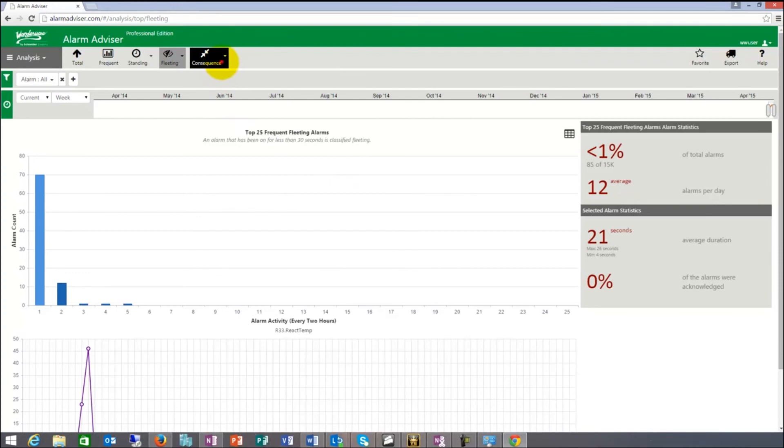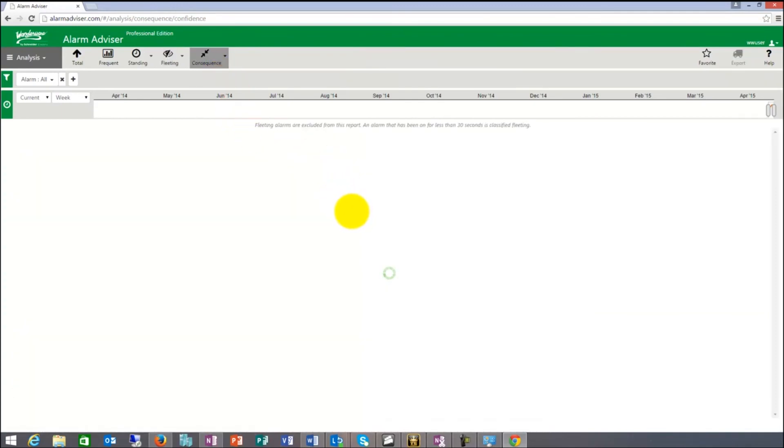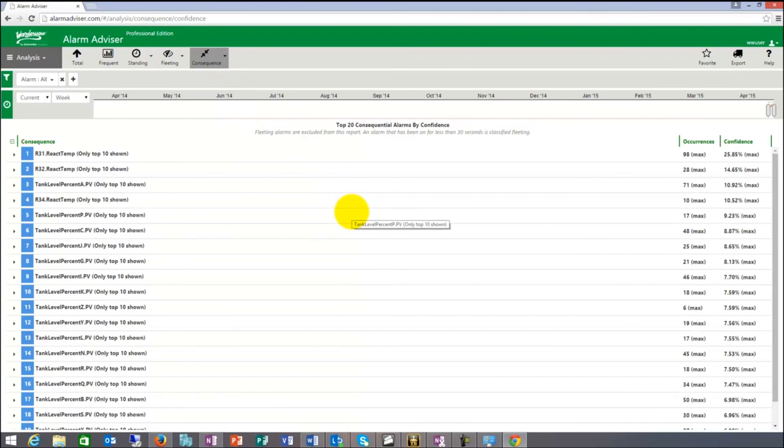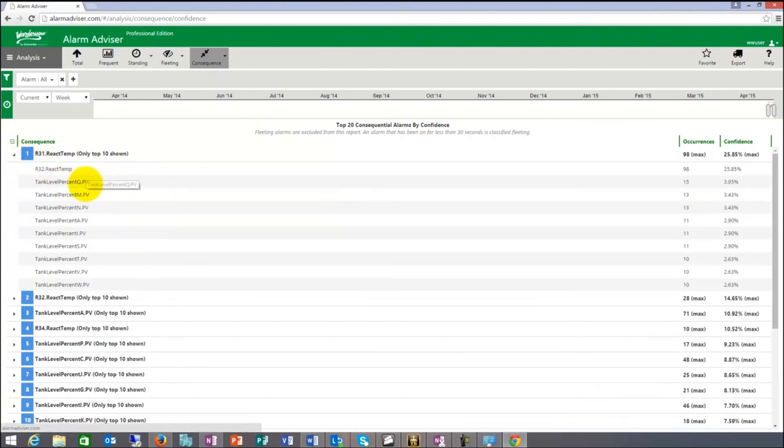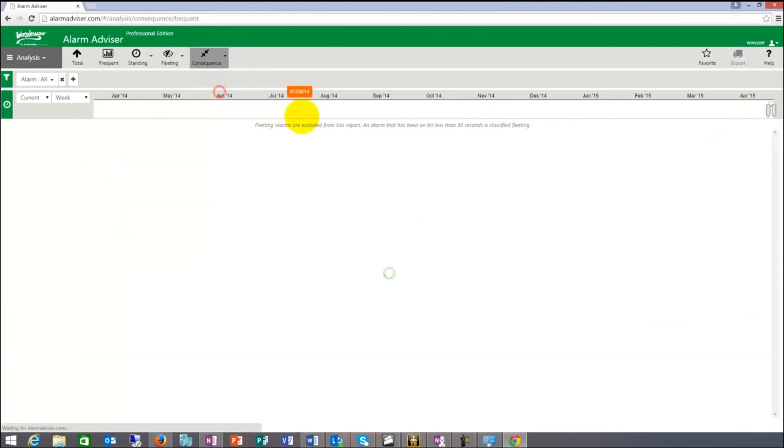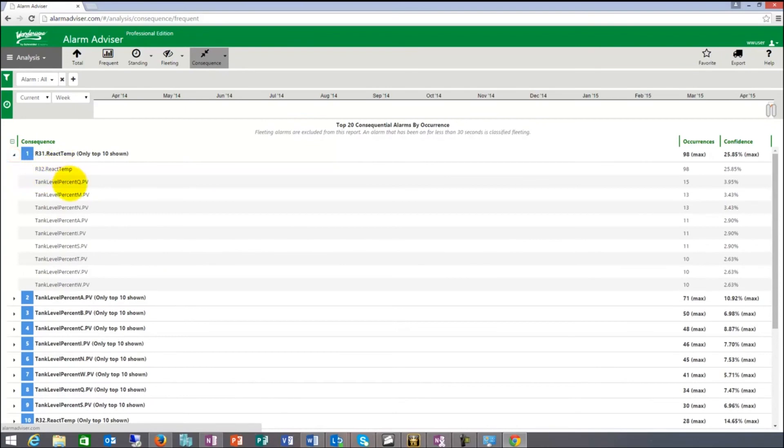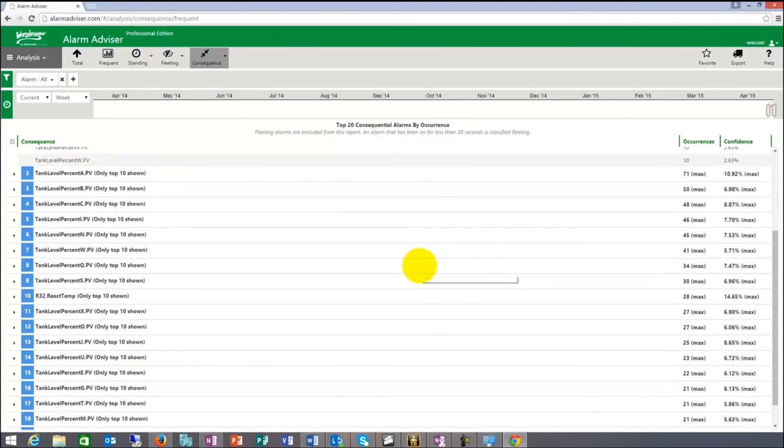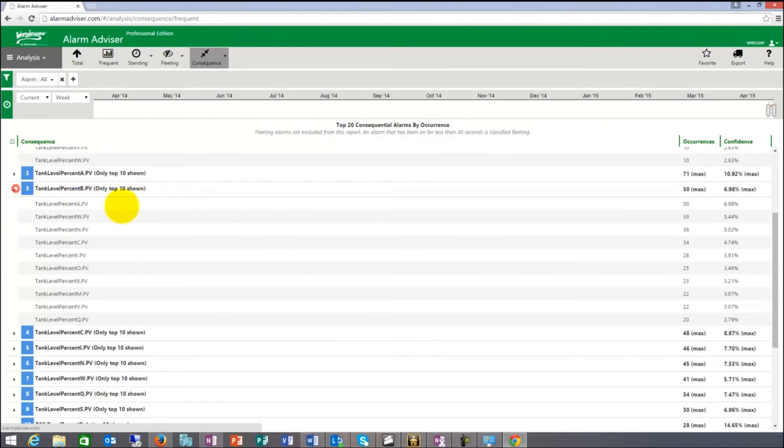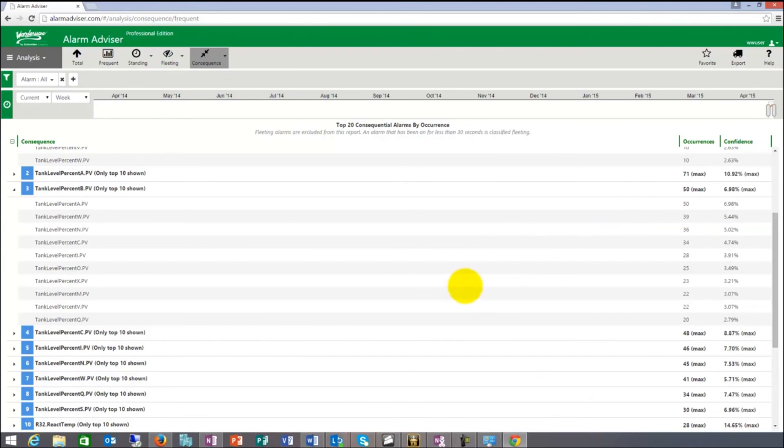The last one that we have is consequential. Consequential is basically determining that within your system, if something happens often, related with that might be other alarms that happen to them. For example, when this happened, this is a very low probability. This is by confidence. If we look by occurrence, by confidence is more like, I can say, reactor temp 98 times and 15 times this one occurred, 13 times. Most likely these don't have a relationship. But there might be some that have a relationship between each other where you can say, hmm, when this goes off 50 times and this goes off 39 times at the same time, are they related? Do they have something to do with each other?